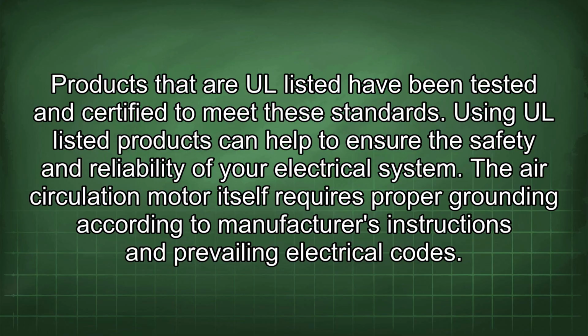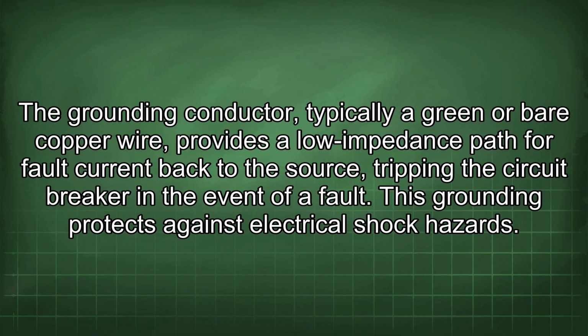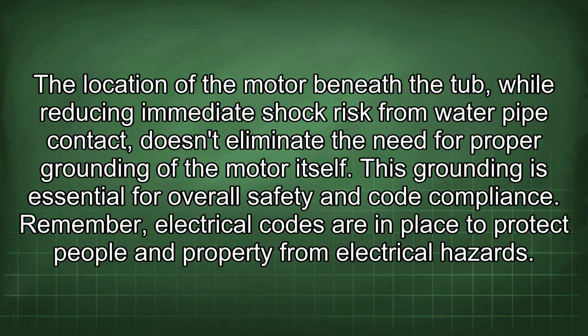The air circulation motor itself requires proper grounding according to manufacturer's instructions and prevailing electrical codes. The grounding conductor, typically a green or bare copper wire, provides a low impedance path for fault current back to the source, tripping the circuit breaker in the event of a fault. This grounding protects against electrical shock hazards. The location of the motor beneath the tub, while reducing immediate shock risk from water pipe contact, doesn't eliminate the need for proper grounding of the motor itself. This grounding is essential for overall safety and code compliance.